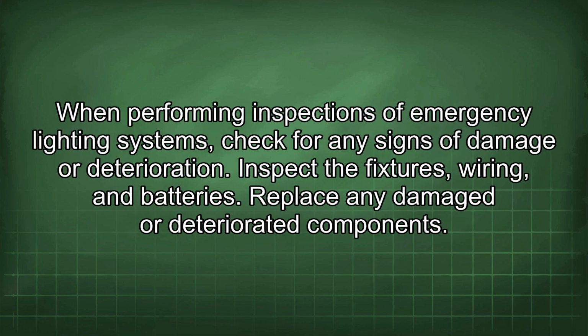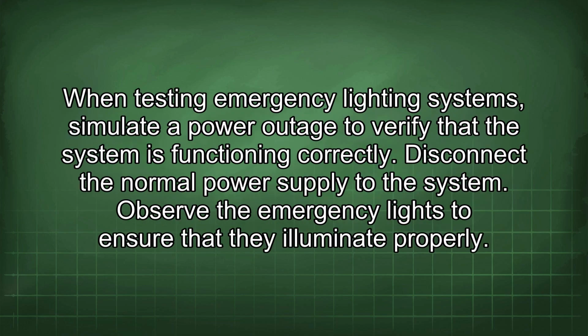When performing inspections of emergency lighting systems, check for any signs of damage or deterioration. Inspect the fixtures, wiring, and batteries. Replace any damaged or deteriorated components. When testing emergency lighting systems, simulate a power outage to verify that the system is functioning correctly. Disconnect the normal power supply to the system. Observe the emergency lights to ensure that they illuminate properly.